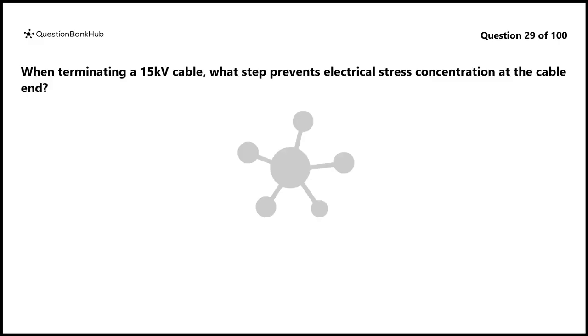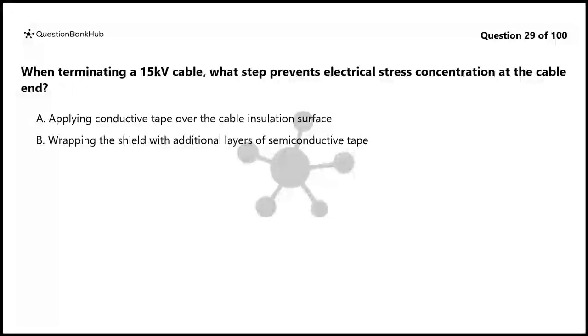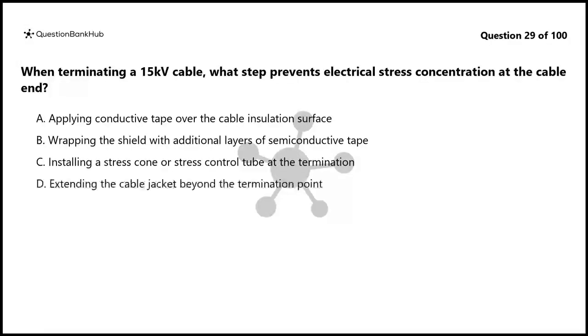Question 29. When terminating a 15 kV cable, what step prevents electrical stress concentration at the cable end? A. Applying conductive tape over the cable insulation surface. B. Wrapping the shield with additional layers of semiconductive tape. C. Installing a stress cone or stress control tube at the termination. D. Extending the cable jacket beyond the termination point.